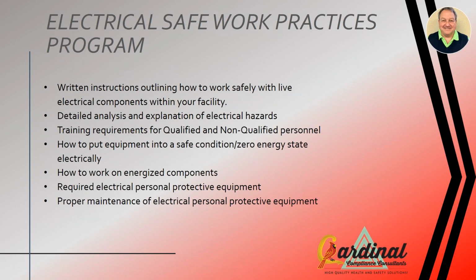You may be a relatively small manufacturer, or you say, I'm going to just do a very bare minimum of electrical work. You may even decide, I'm so small, I'm just calling an electrical contractor if I have a problem. That's okay. It's your facility. You get to make the decision. Now, there are many large manufacturers where I can't afford to wait for an electrician to show up. I have to have my own people fully trained, fully qualified to work on anything that I have in my facility. So that's why the different procedures are required, and that's also why you get to set the standard for who is electrically qualified in your own facility.